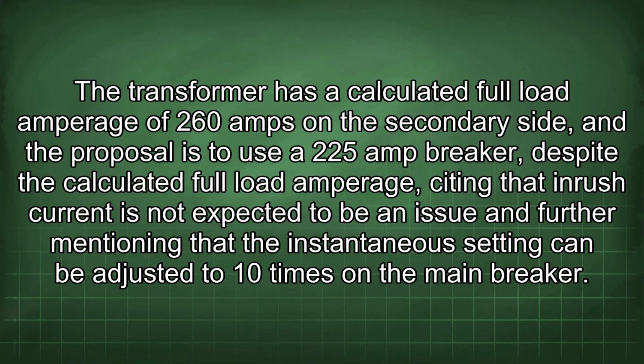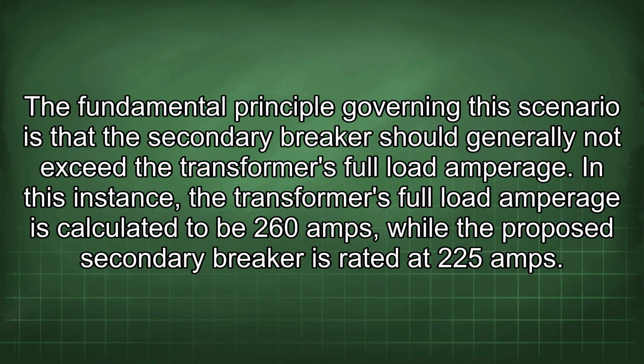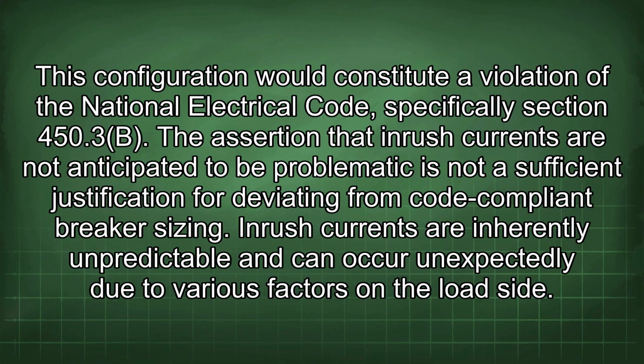main breaker. The fundamental principle governing this scenario is that the secondary breaker should generally not exceed the transformer's full load amperage. In this instance, the transformer's full load amperage is calculated to be 260 amps, while the proposed secondary breaker is rated at 225 amps. This configuration would constitute a violation of the National Electrical Code, specifically Section 450.3b.